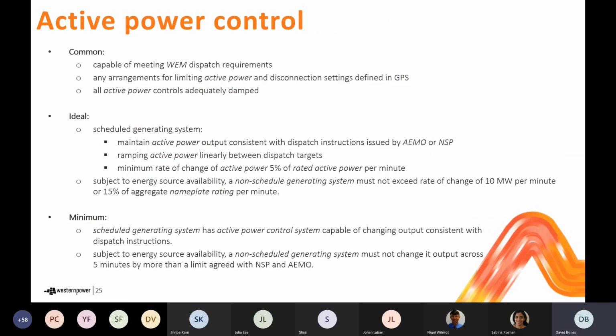So we'll just move on to the next one, which is active power control capability. So again, this is one that has a common requirement, ideal and minimum standards. So to meet the ideal standards for active power control, a large generating system that is scheduled must be able to follow dispatch instructions that are issued by AEMO or the NSP, ramp linearly between dispatch targets, and achieve a minimum rate of change of 5% of rated active power per minute. Non-scheduled generators meeting the ideal standard must, subject to energy source availability, not exceed a rate of change of greater than 10 megawatts a minute or 15% of the nameplate rating per minute.